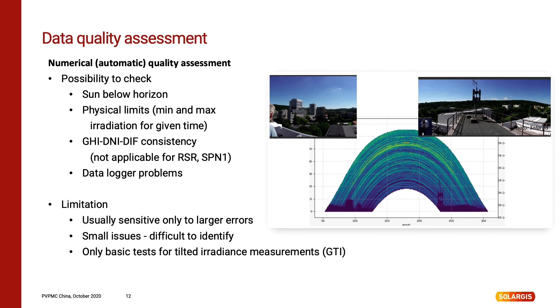The fourth step of data quality assessment is automatic quality check based on numerical methods. With a Solar Geometry algorithm it is possible to detect when the Sun is below the horizon. Irradiation at a given time may appear only in a given theoretical range of minimum and maximum values, thus all outliers can be rejected. Automatic quality check can also detect some data logger problems where values are not recorded properly, resulting in high, low or unchanging records. The limitation of this method is that it can usually detect only larger errors. Small defects are hard to detect, so that is a task for visual inspection. There are only some basic tests available for tilted irradiance measurements, and due to additional factors it is hard to perform good quality control of tilted irradiance.